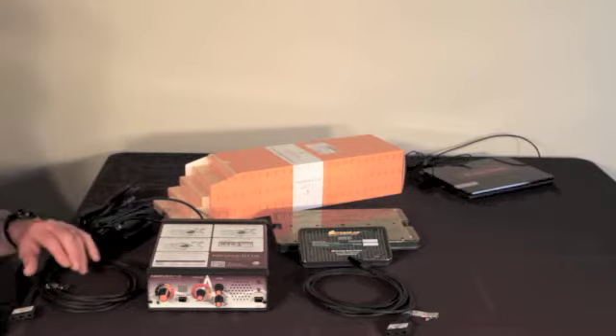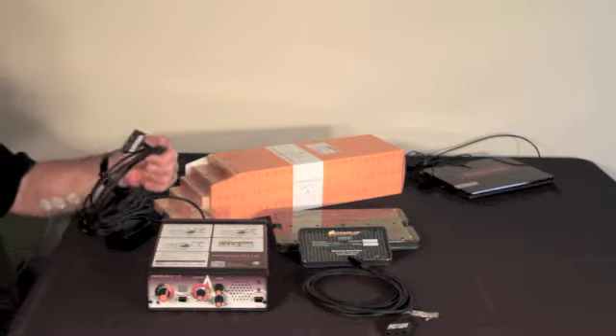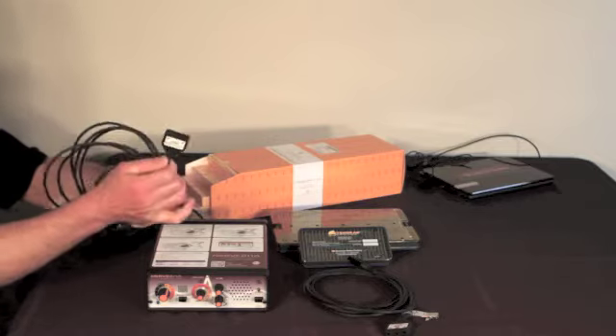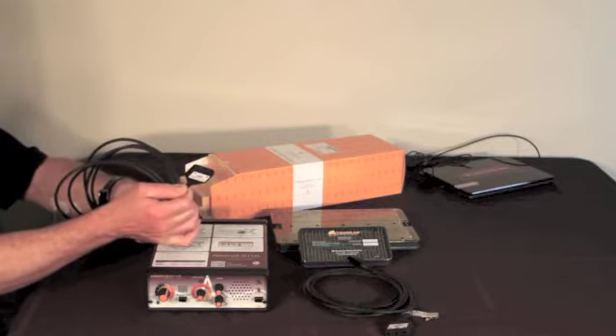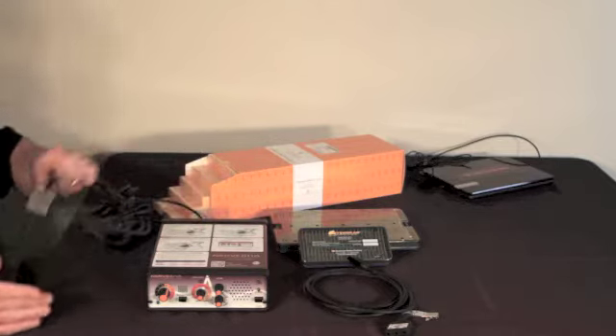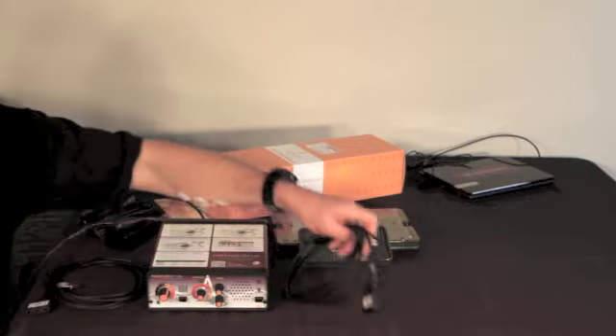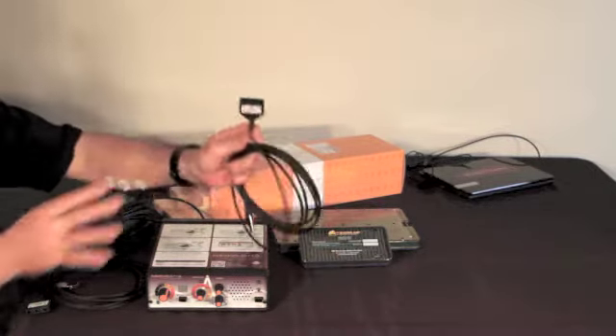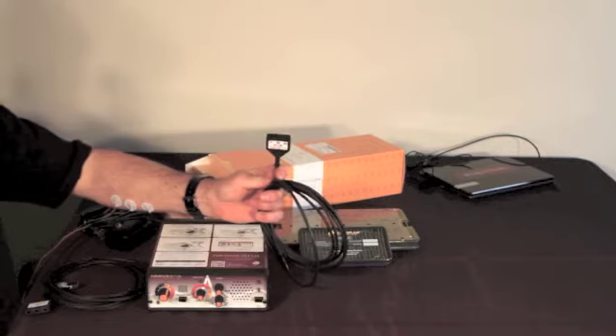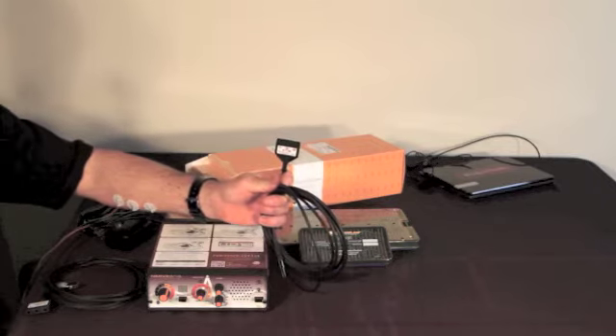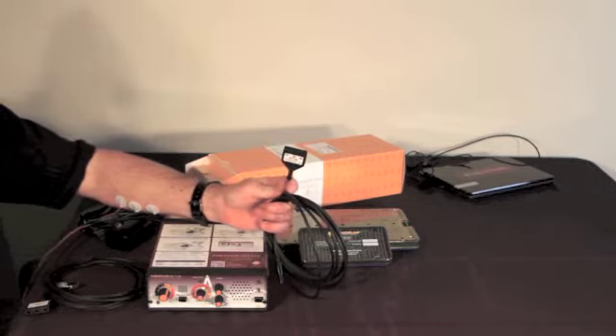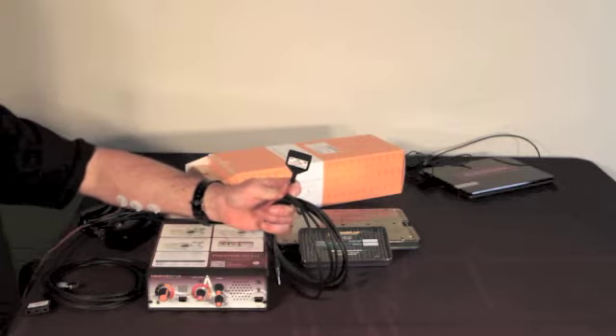Every surgery kit setup is going to involve placing monitoring electrodes on the patient and connecting to this EMG cable using color-coded ports. And then after that, setting up a stimulator cable with a lead coming off the sterile field that goes to a stimulator probe that's used by the surgeon.